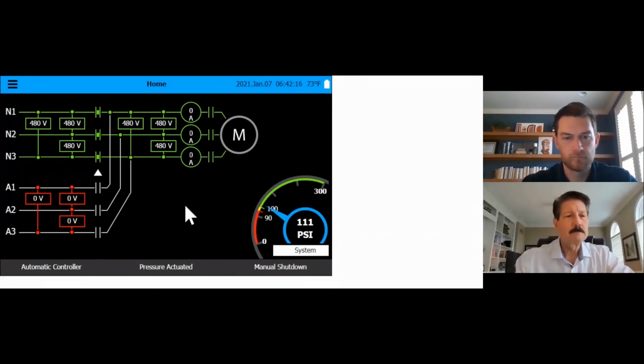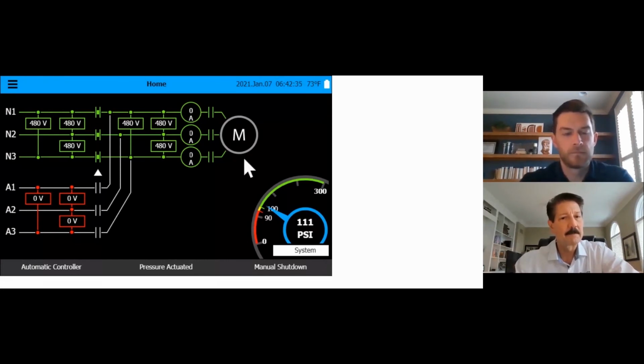So it is possible when you're checking this, that if you do have a generator running, you'll see green and voltage reading in these boxes, but you can have the normal side and the genset running at the same time because only one will be connected in linkage to the motor itself. So again, if this did not have a generator, then the bottom part here wouldn't be here. It would just be the top part that's green.